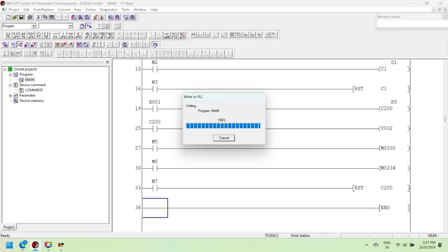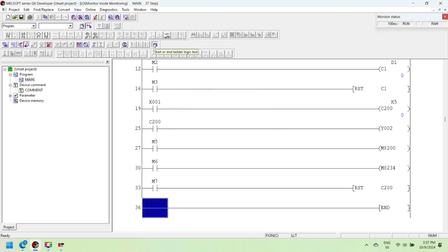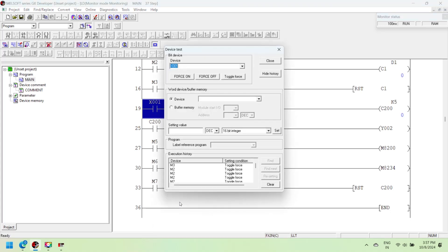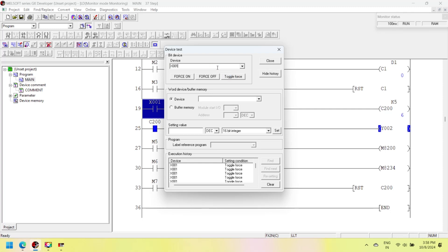The counter's current value increases or decreases independently of the output contact state. If a counter counts beyond the 32-bit maximum value, the current value will automatically change to the 32-bit minimum value. Similarly, counting below the 32-bit minimum value will result in the current value changing to the 32-bit maximum value — this type of counting technique is typical for ring counters. If both M8200 and M8234 are turned off, the counter works as an up counter. If M8200 is turned on and M8234 is turned off, the counter works as a down counter.